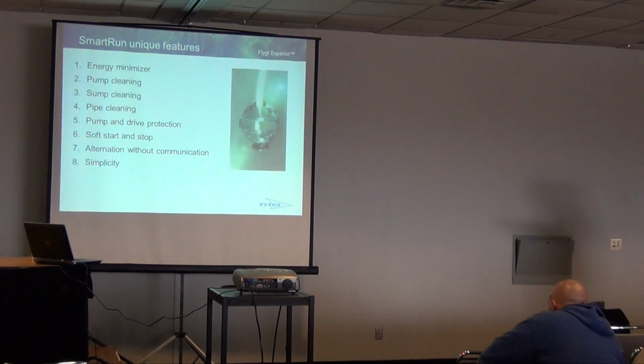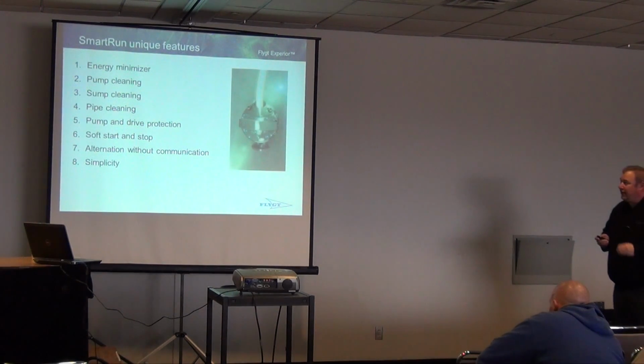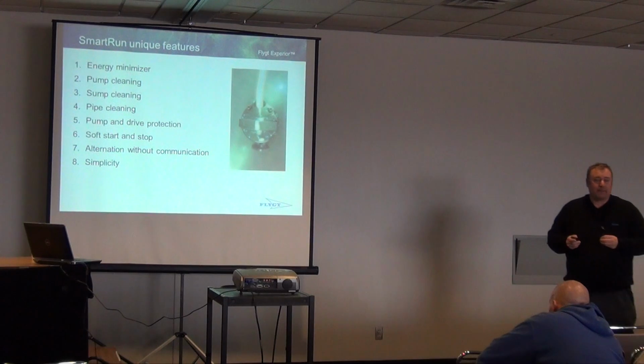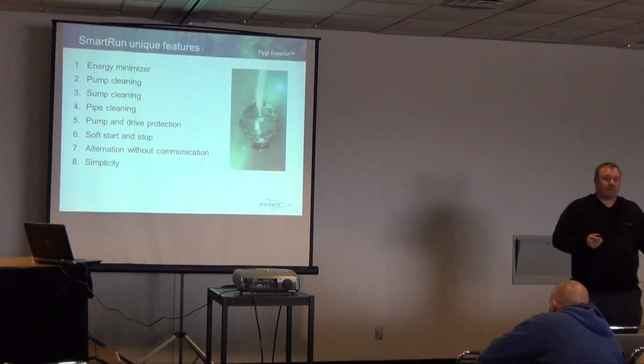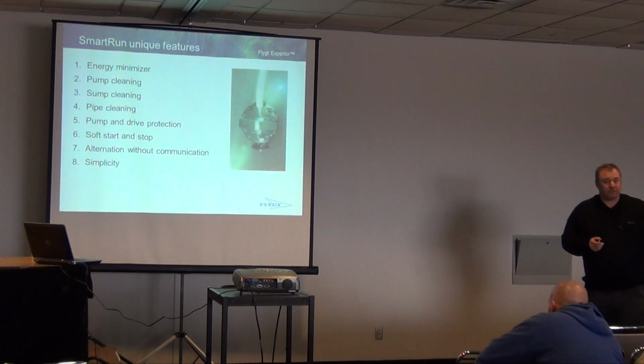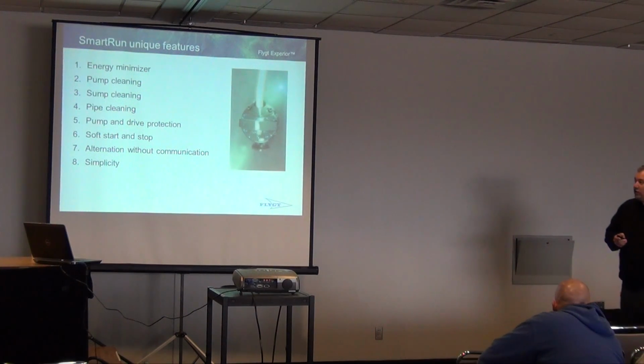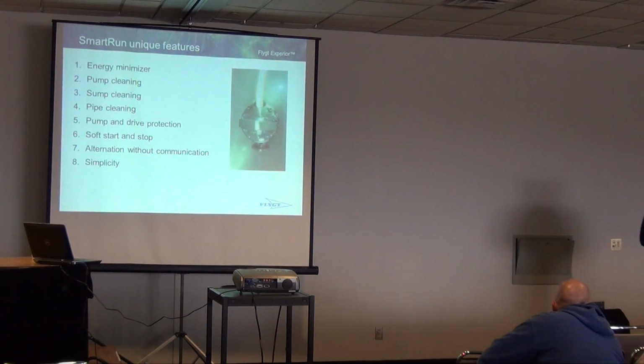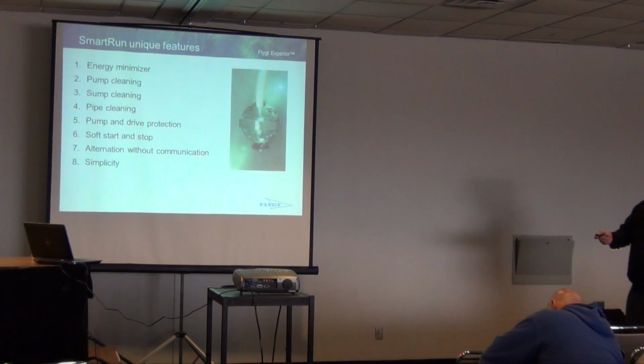It also has pump and drive protection, which we talked about. Our overtemp and our leakage is built into the unit. It has a soft start and stop. So we can ramp the unit up slowly like you would with a variable frequency drive. You can actually slow the pump down slowly so you're not getting water hammered, things like that in your system. So that's built-in functionality into this unit.